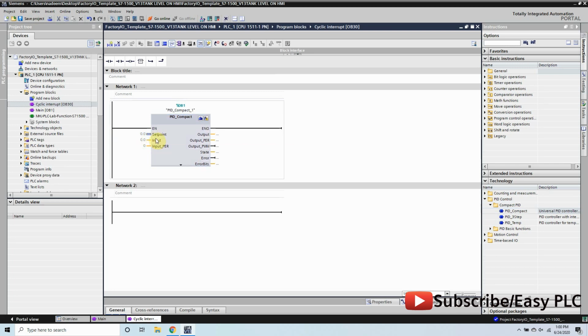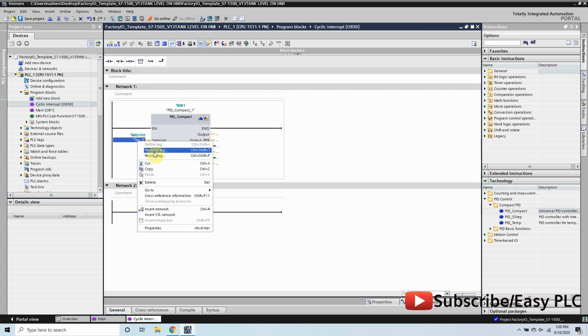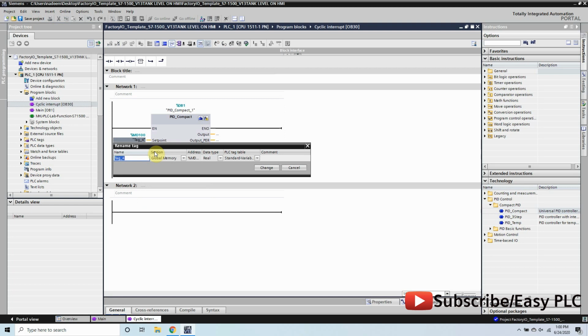Input is the analog value coming from a data register or data block, like in our case, it is the scaled tank level in MD10 memory word. Input_PER is the peripheral analog input. We can assign the PLC analog input directly to the PID command using this input.